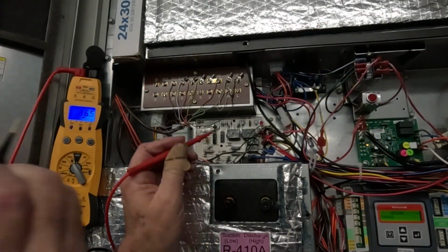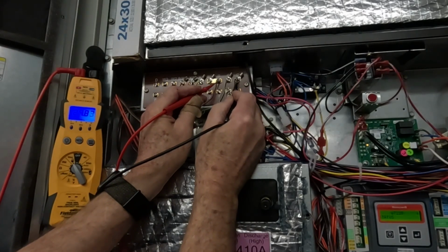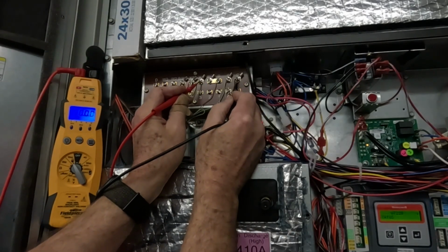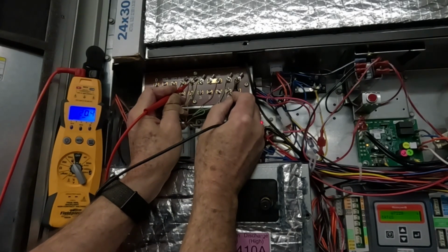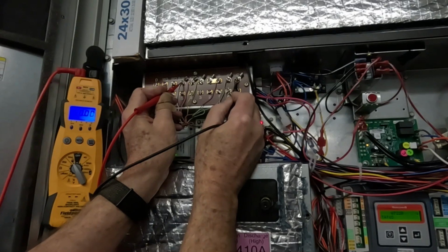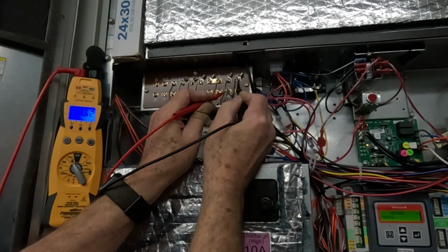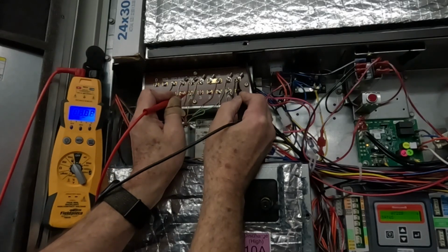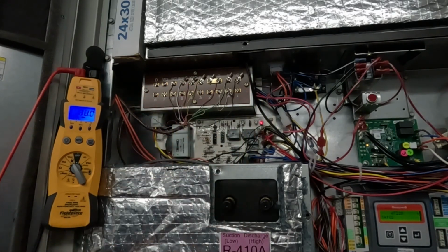Next, take your meter and see what low voltage terminals have 24 volts to common. R and RT should. Do any of the others? This will tell you what modes are calling. Does L have 24 volts to common? If so, you have either a high or low pressure switch trip. Both current Bard heat pumps and AC units have an L terminal. Resetting the circuit breaker will reset the board, but that may not solve your problem.